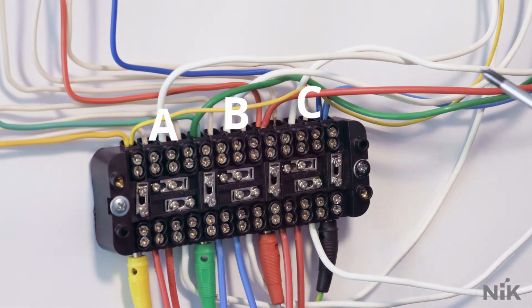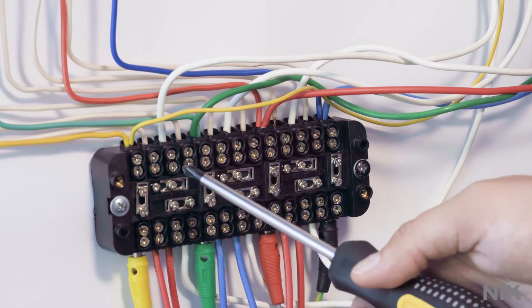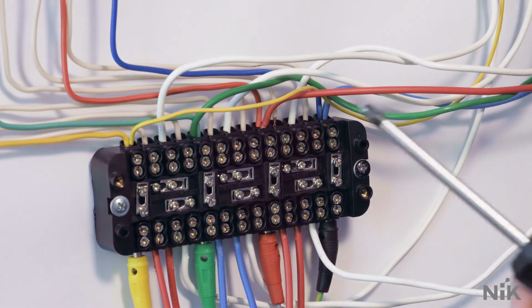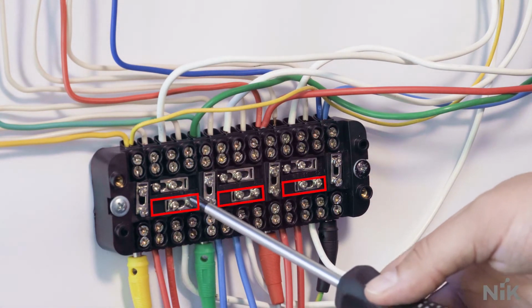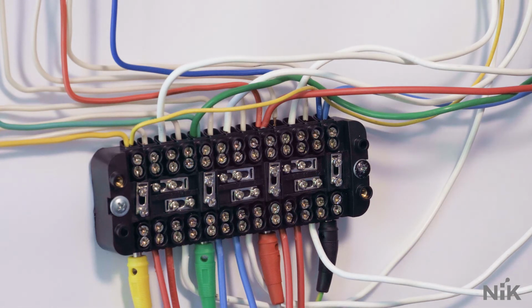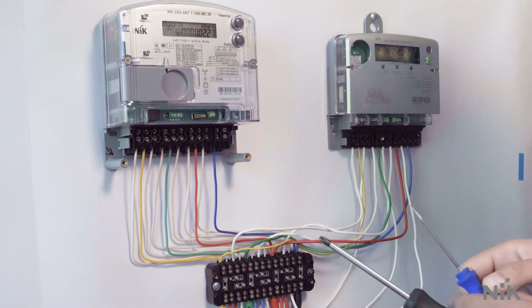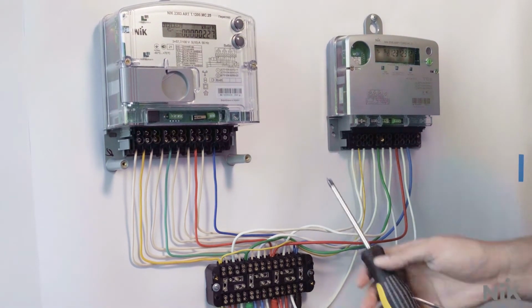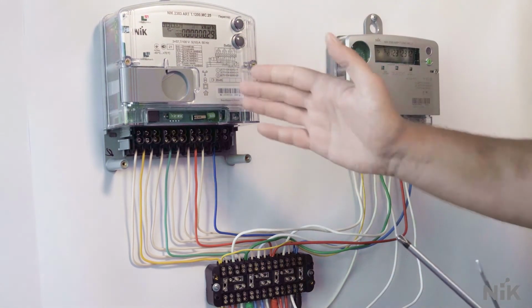Upper jumpers are used for shorting of current transformers, that is secondary circuits, which allows to work with device without load. Lower jumpers are used for connection of doubling or echelon devices into the circuits. At the beginning, we shorten current circuits for safe mounting and dismantling of this device.